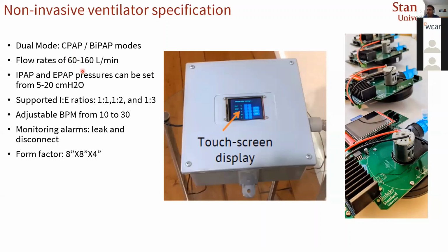And also flow rates are quite important. You need a decent flow rate, because if you don't maintain that flow inside the helmet, there is a possibility of CO2 rebreathing. So that's why we needed to do experiments to find out the minimum flow rate. And also we can do pressure profiles from 5 to 20 centimeters of water. IE ratio is essentially the inspiratory to expiratory cycle ratio. And also we can do different breaths per minute. And it has an alarm for monitoring leak and disconnection. And the whole thing fits inside an 8-inch by 8-inch by 4-inch box. It's super portable.